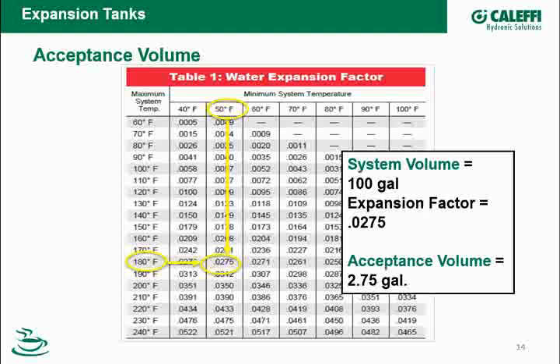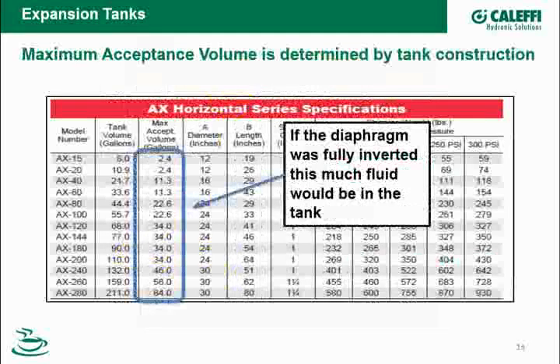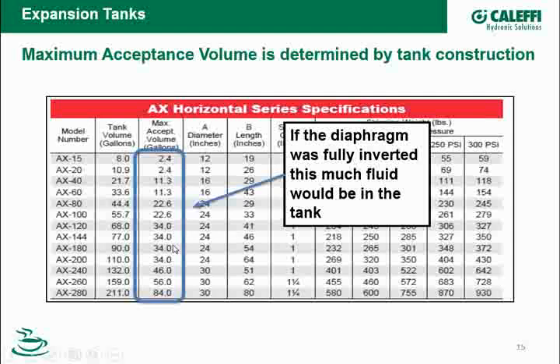So this becomes one of the criteria we start looking at for expansion tank sizing. This is important information that's needed to pick the right size tank. Now, something that manufacturers do print, I would say pretty much everybody has it somewhere in their literature, is what's called the max acceptance volume. For instance, this is off of Amtrol's website, their AX series diaphragm tanks. This max acceptance volume column represents the volume of water I can support or hold in that diaphragm if I fully invert it.